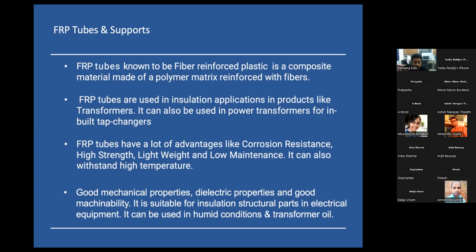Yes, sir. I am dealing with FRP tubes and supports. FRP tubes are fiber reinforced plastic, a composite material made of a polymer matrix reinforced with fibers. FRP tubes are used in insulator applications in power transformers for inbuilt tap changers. FRP tubes have a lot of advantages like corrosion resistance, high strength, and withstanding high temperature. Good mechanical and electrical properties and good machinability are also there in FRP tubes.